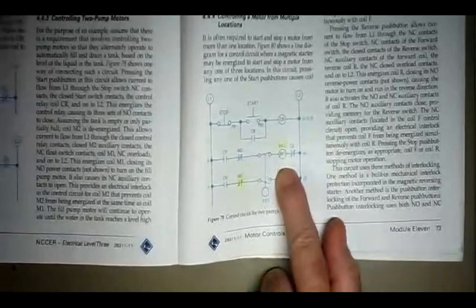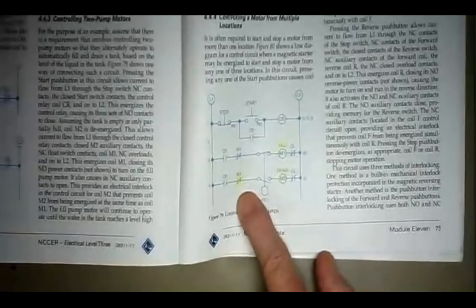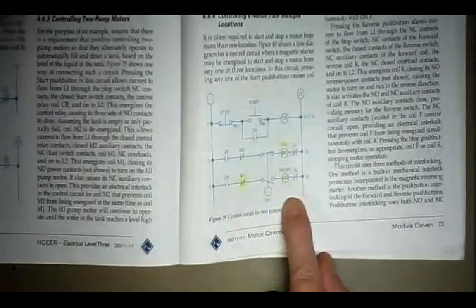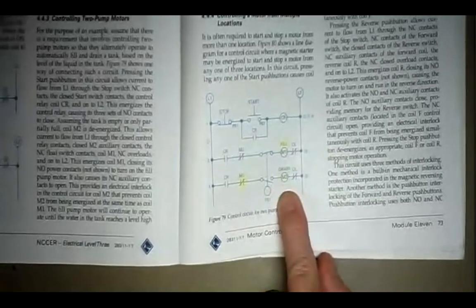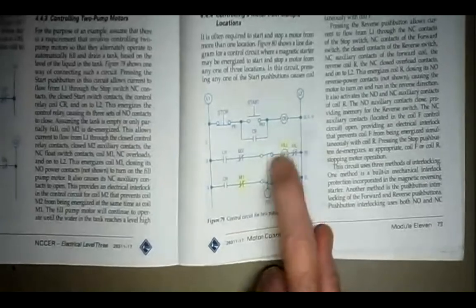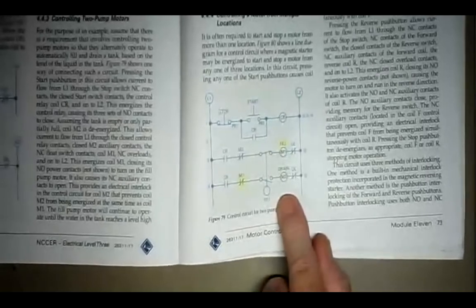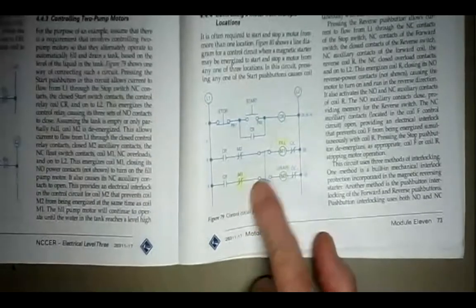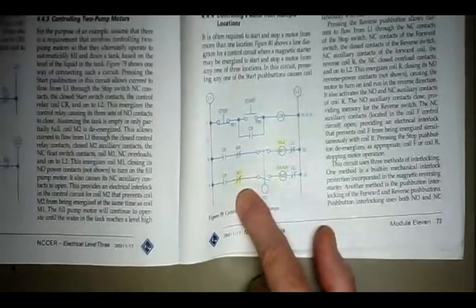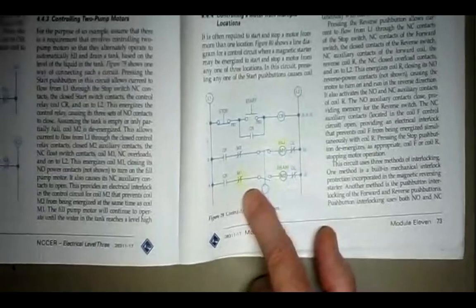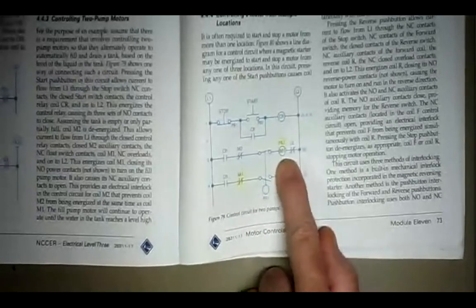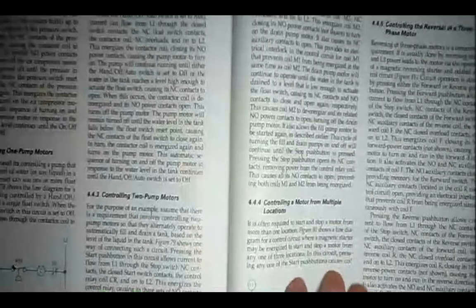When the fill pump is on and you're filling the tank, this normally closed contact M1 is open, not allowing you to start the drain pump. So you can only run either the fill pump or the drain pump at a time. But they may ask you something about that. What's the M1 contact in line 4? What is its purpose? To make sure that the drain pump is not energized when the fill pump is operating. You can only do one or the other. You can't do them both. Those are called electrical interlocks.